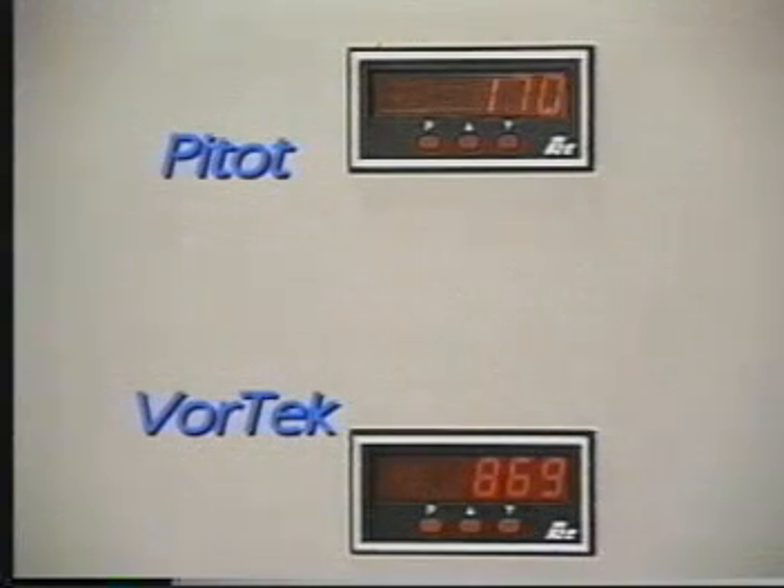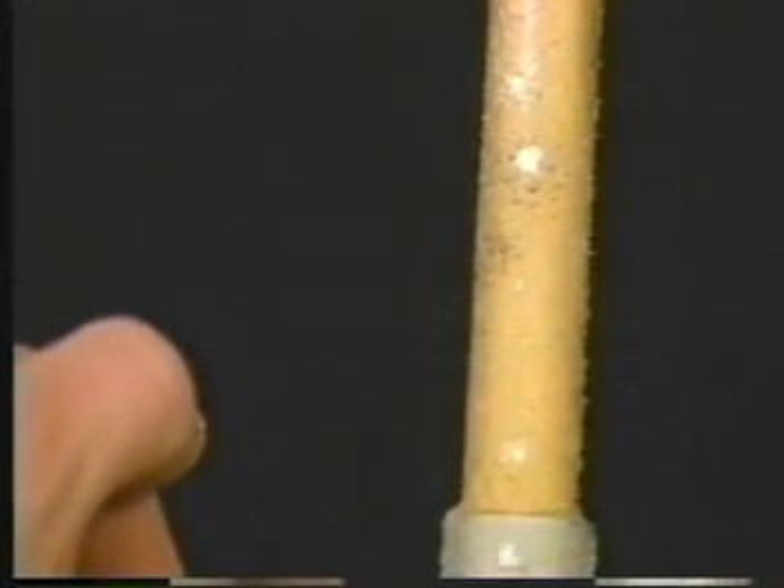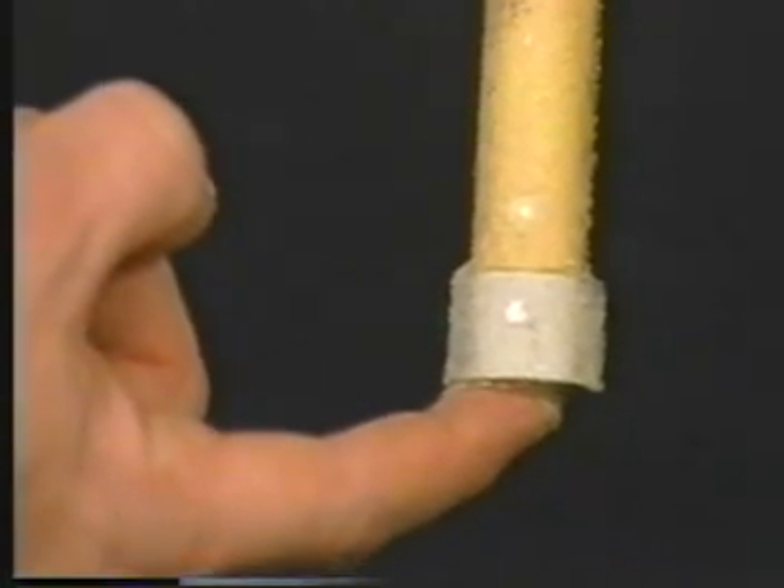Flow velocity, which is in the neighborhood of 900 feet per minute, is accurately reflected. As you can see, the pressure ports of the Pitot sensor, which are in direct line with airflow, have been clogged, and that's why the reading measuring flow has dropped off — an indication that this type of probe and most Pitot probes are prone to clogging of the pressure ports.